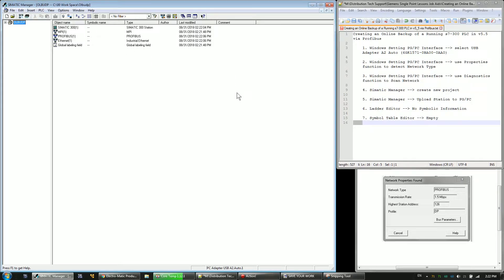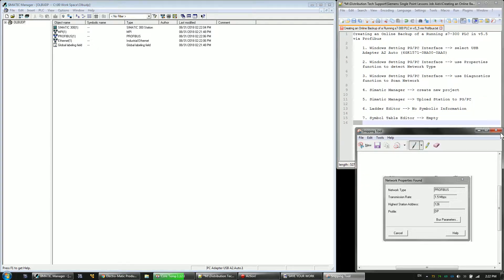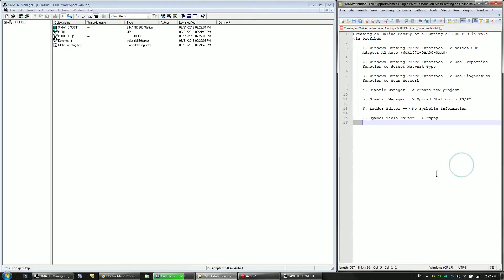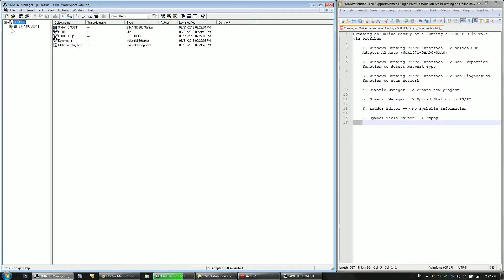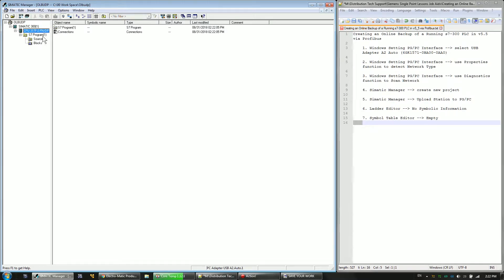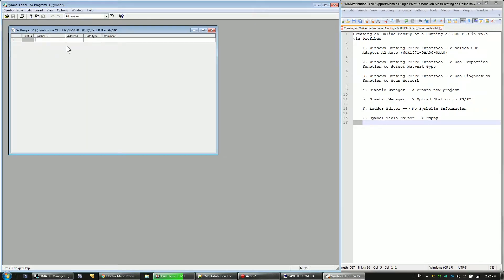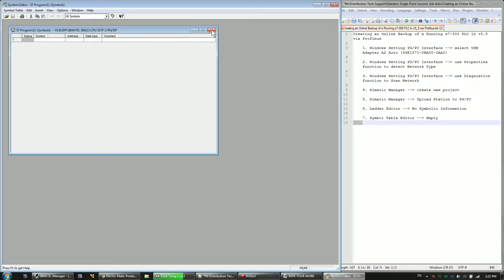And I've uploaded the project here. So the thing about uploaded projects, regardless of whether you're using Ethernet, like our last video or PROFIBUS, they don't have any symbolic information. So what that means is the symbol table will be empty on an uploaded project.